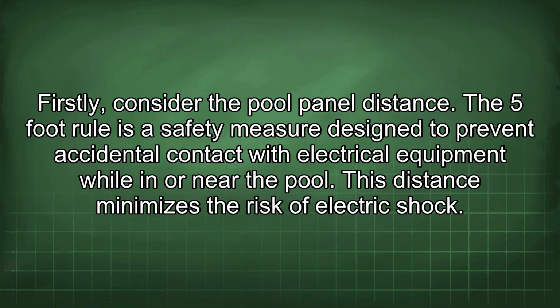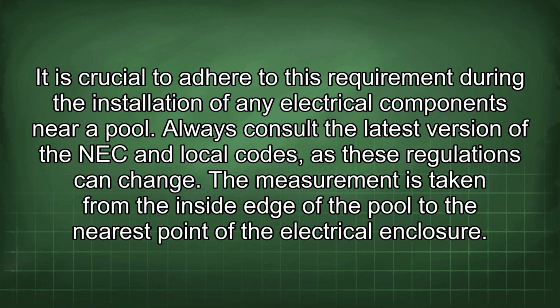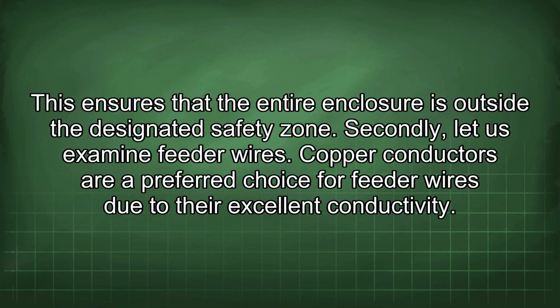Firstly, consider the pool panel distance. The 5-foot rule is a safety measure designed to prevent accidental contact with electrical equipment while in or near the pool. This distance minimizes the risk of electric shock. It is crucial to adhere to this requirement during the installation of any electrical components near a pool. Always consult the latest version of the NEC and local codes, as these regulations can change. The measurement is taken from the inside edge of the pool to the nearest point of the electrical enclosure. This ensures that the entire enclosure is outside the designated safety zone.